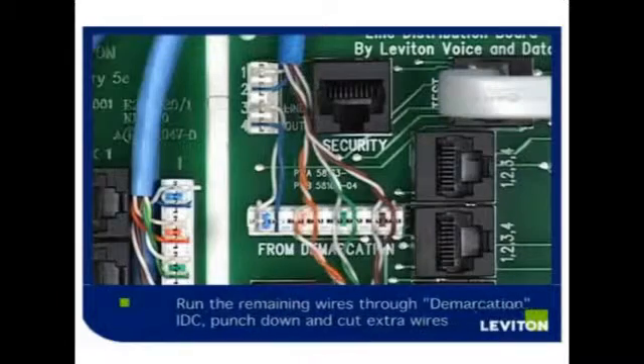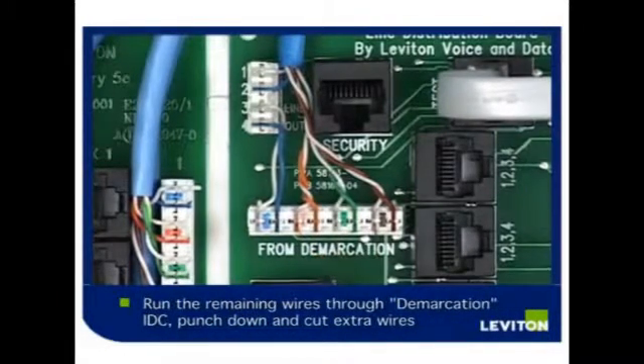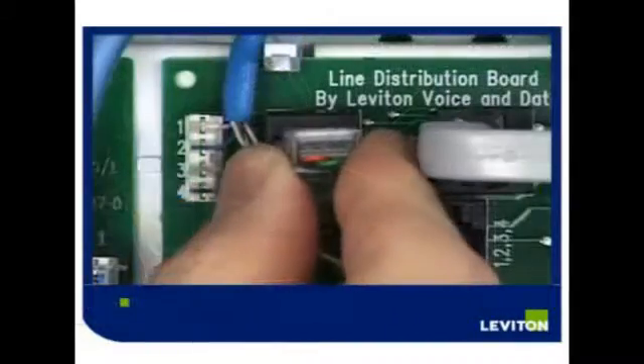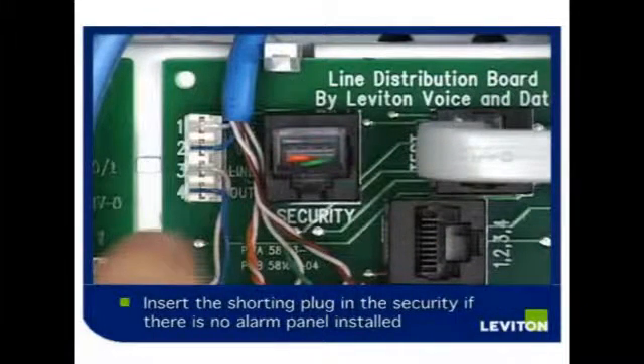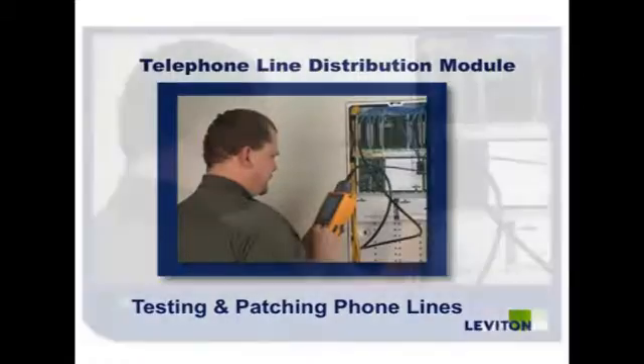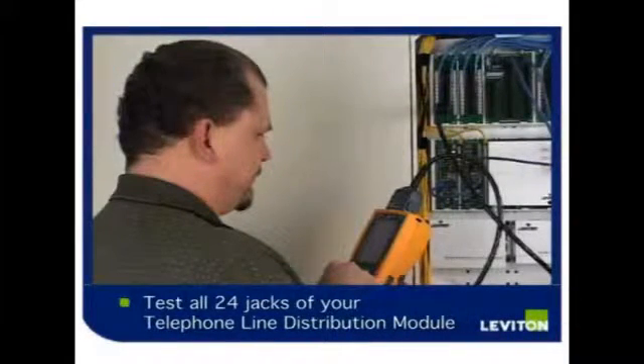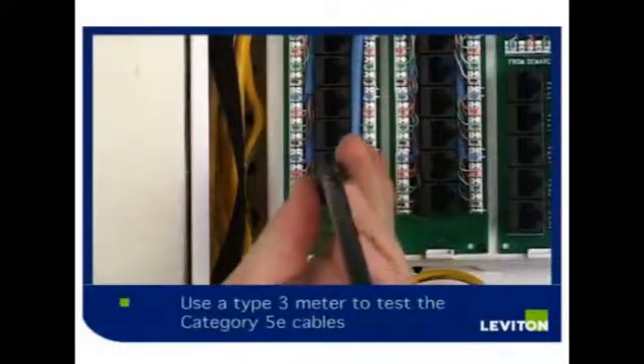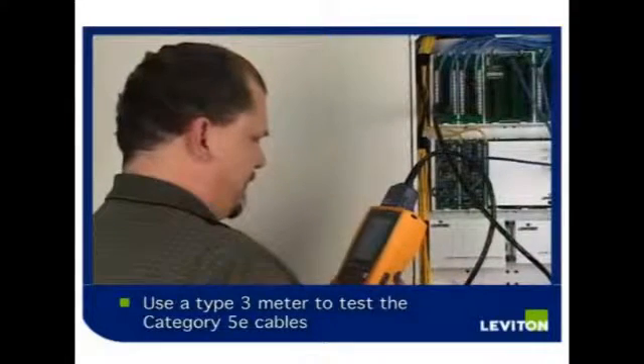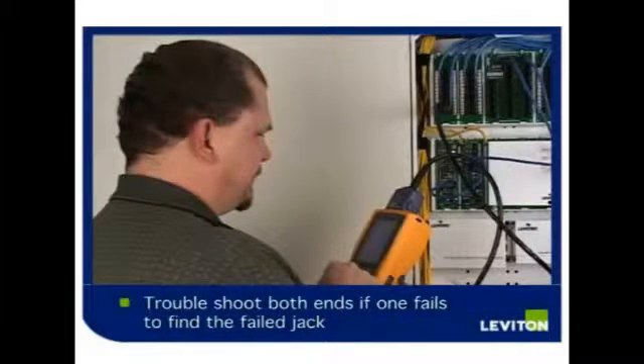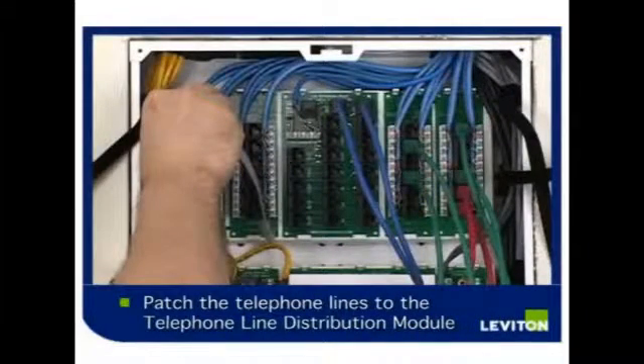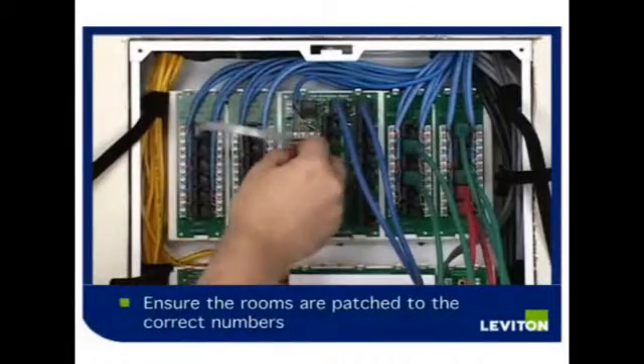Route your remaining three phone lines through the from-demarcation IDC and punch them down. If there is no alarm panel currently installed, insert the shorting plug. This will route your line from the IDC back through the in-from-demarc IDC. You will need to test all 24 jacks of your telephone line distribution module. Using a type 3 meter for the Category 5 cable, test all 24 jacks, ensuring they all pass. If one fails, you will need to troubleshoot both ends of the wire to find the failed jack. Now patch your phone lines to the telephone line distribution module, patching only specific rooms for specific numbers.